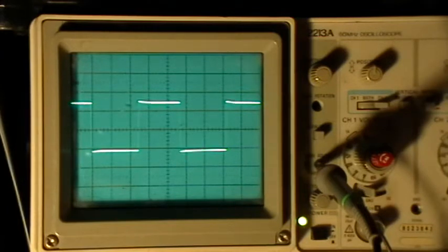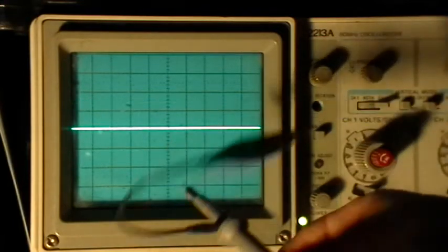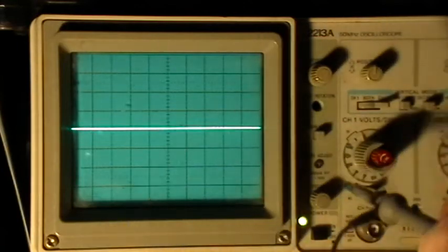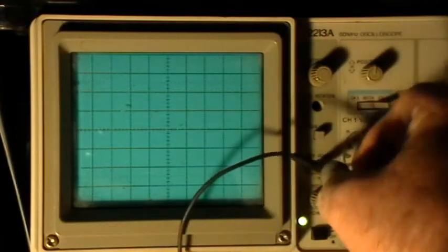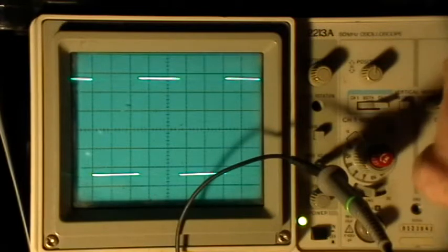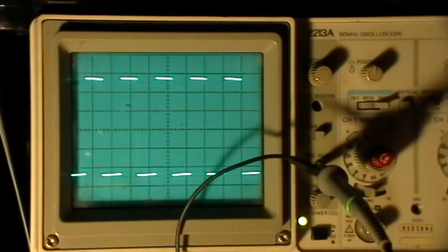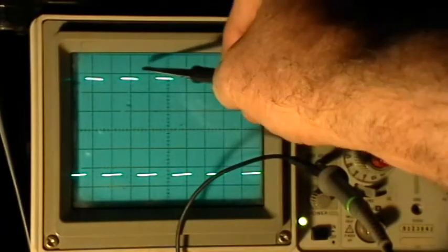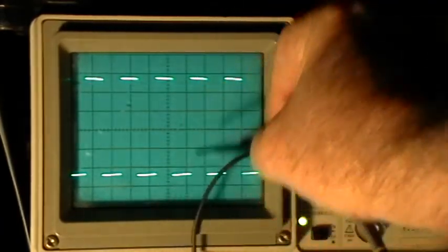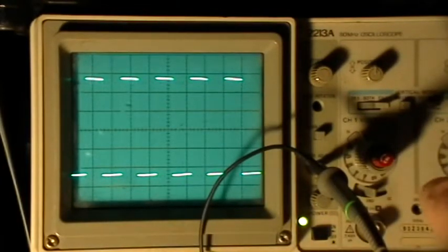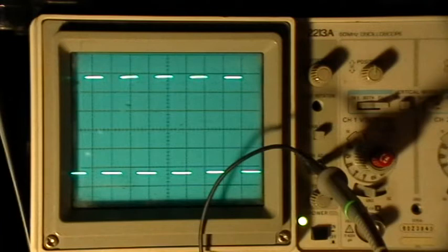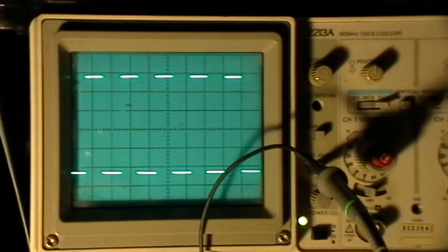And what I want to do is turn that capacitor to where I get the squarest possible or flattest possible shape, like that. Now the probe is adjusted properly. Once again though, if I switch now to 1x attenuation and leave it on AC coupled, you can see that it has that downward slope or upward slope like that. In the DC coupled condition, it's nice and flat straight across.